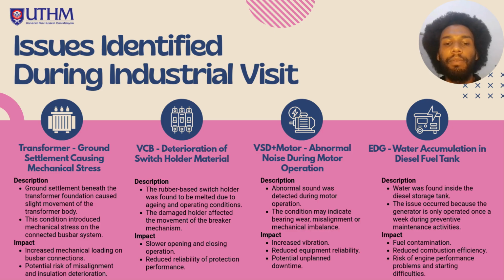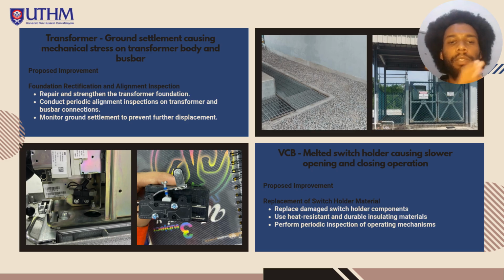The last thing is for the emergency diesel generator. Excessive water accumulation was found inside the diesel fuel tank due to infrequent operation. So here are the suggestions for improvement. Firstly, for the transformer, foundation rectification and periodic alignment inspection are recommended to prevent further settlement and displacement stress. For the vacuum circuit breaker, the damaged switch holder should be replaced with more heat-resistant material.